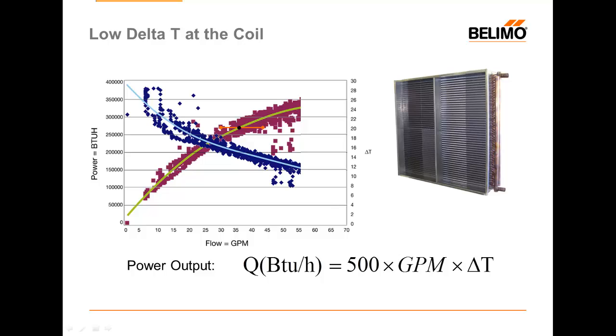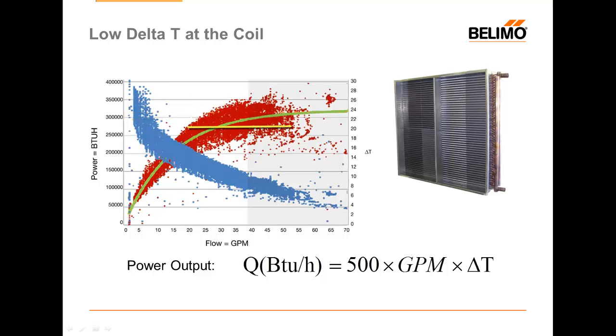This curve has been truncated at a point where it is no longer efficient to pump additional water. However, if we continue pumping water, my coil curve is now completely flattened out and I'm no longer producing BTUs. The only thing that happens if I increase flow now is that I reduce my overall delta T.